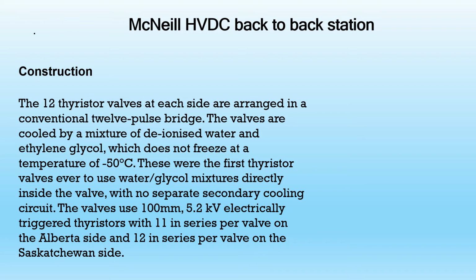The construction of the McNeill back-to-back station: the 12 thyristor valves at each side are arranged in a conventional 12-pulse bridge. The valves are cooled by a mixture of deionized water and ethylene glycol, which does not freeze at a temperature of -50 degrees Celsius. These were the first thyristor valves ever to use a water glycol mixture directly inside the valve, with no separate secondary cooling circuit. The valves use 100 mm 5.2 kV electrically triggered thyristors, with 11 in series per valve on the Alberta side and 12 in series per valve on the Saskatchewan side.